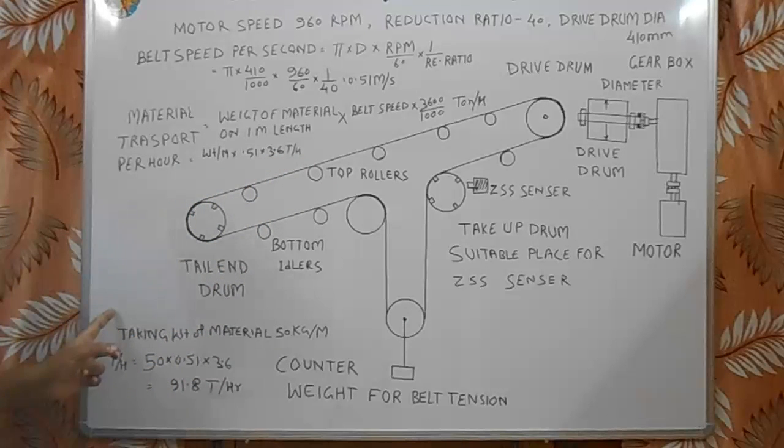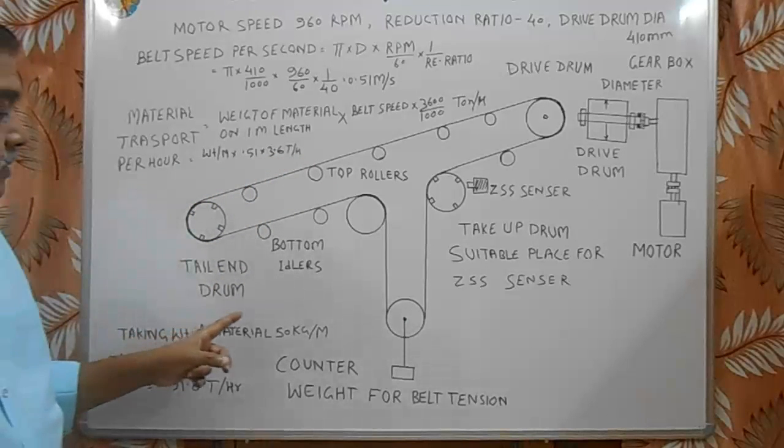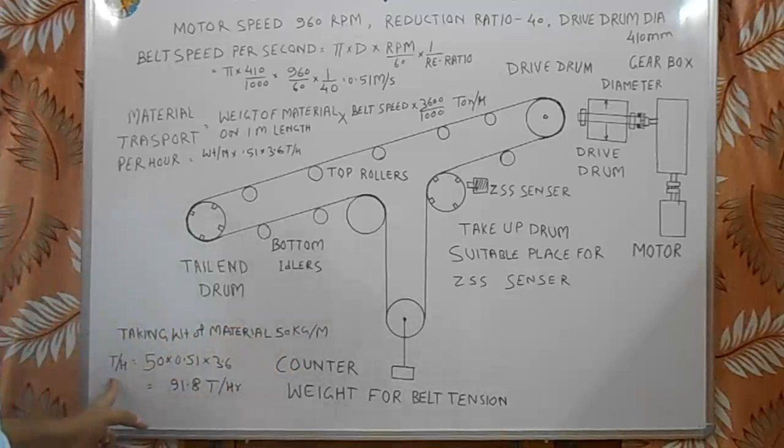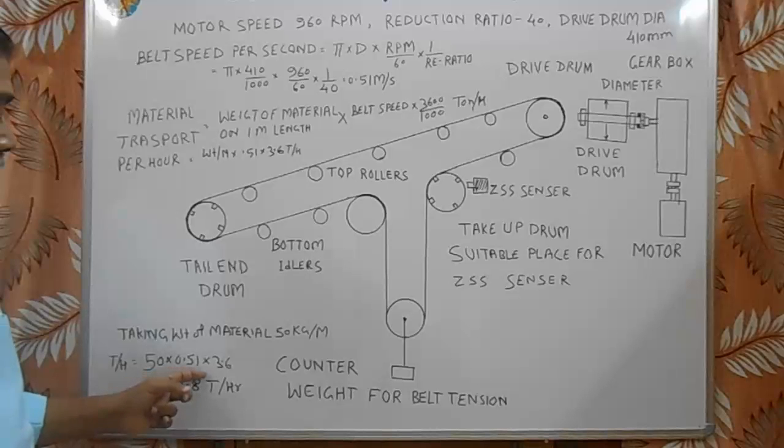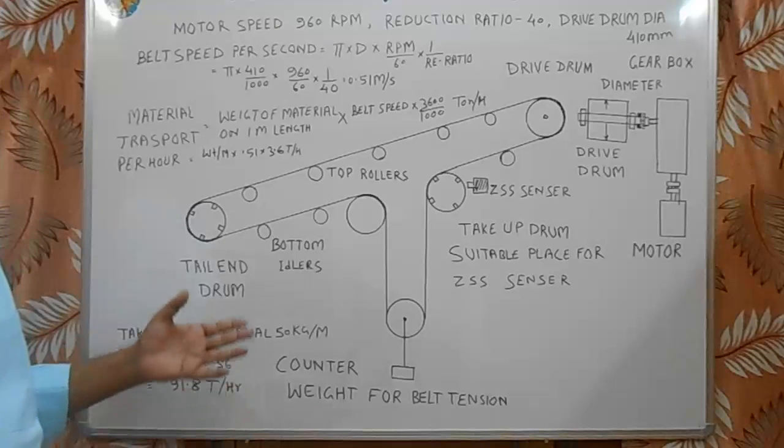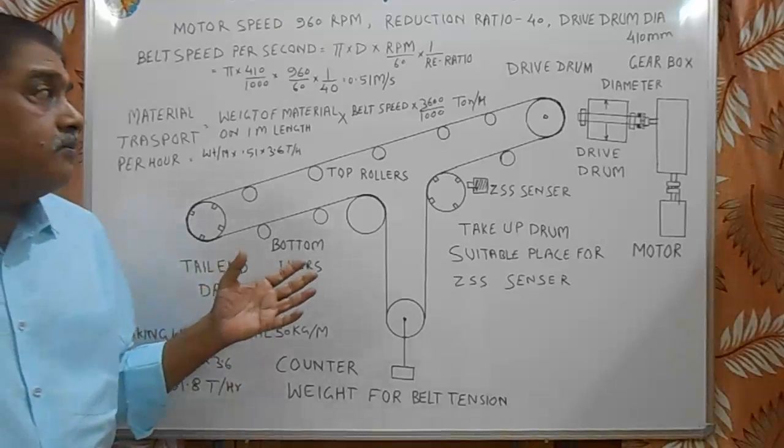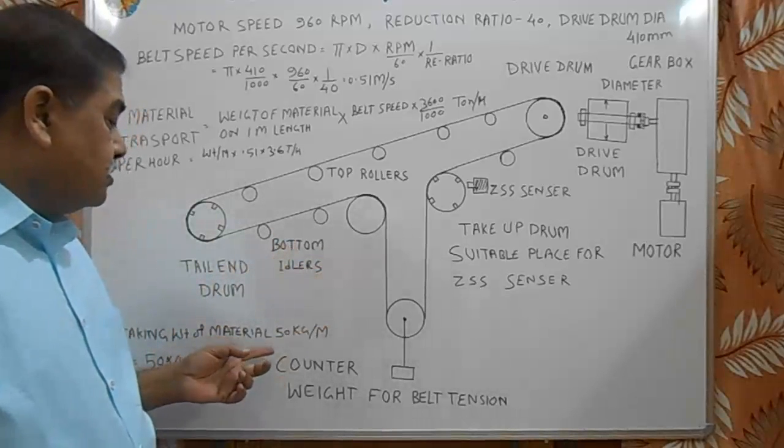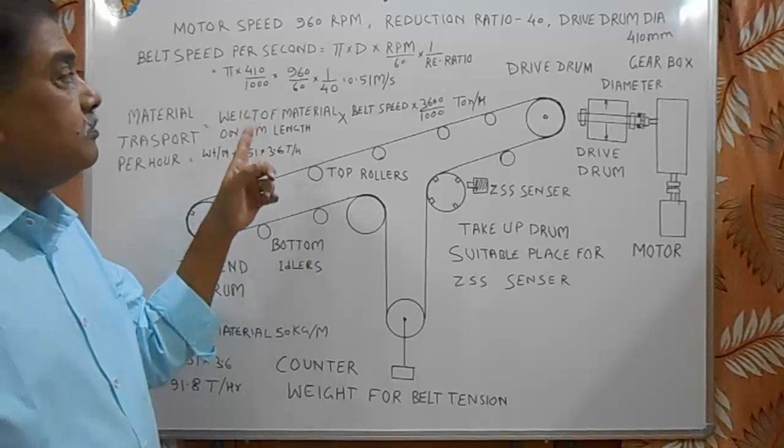Here we are taking weight of material 50 kg per meter. So calculating, tons per hour is equal to 50 into 0.51 into 3.6 is equal to 91.8 tons per hour. So for any belt conveyor we can calculate the material transported per hour with this formula.